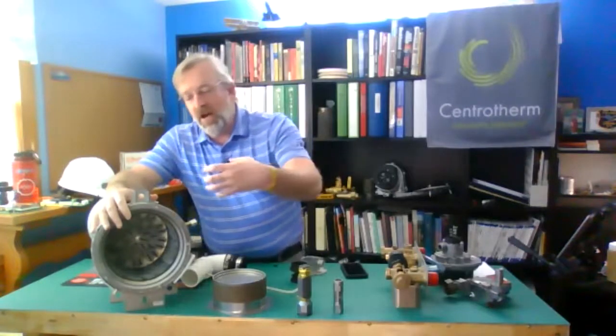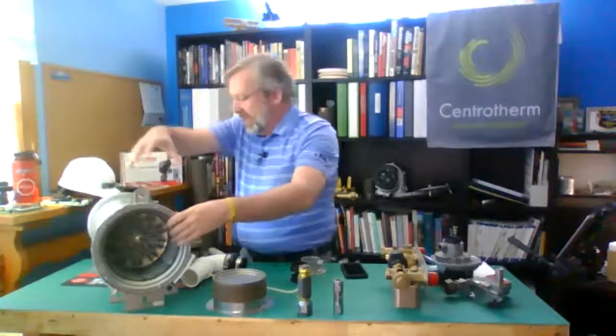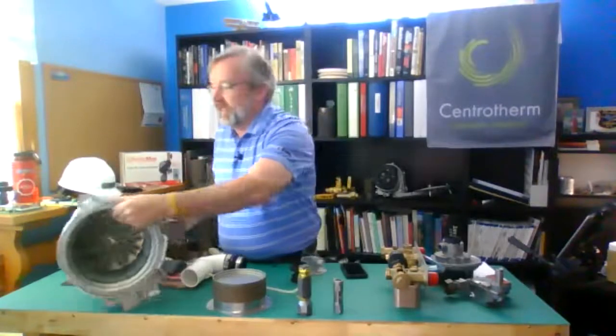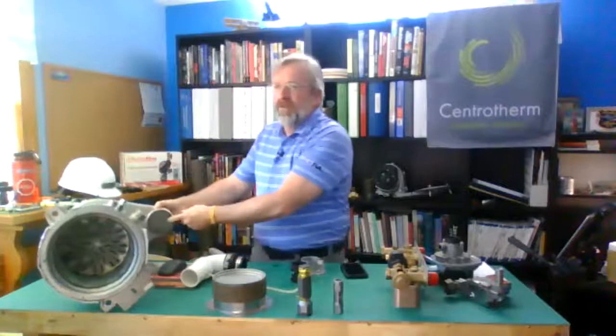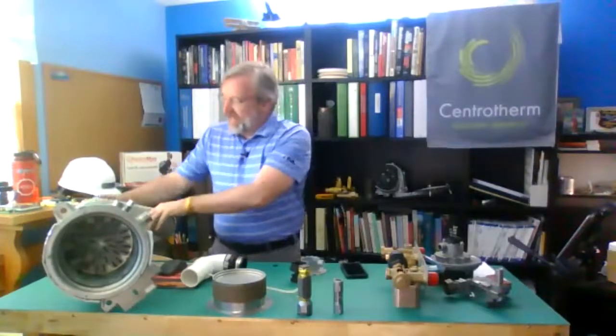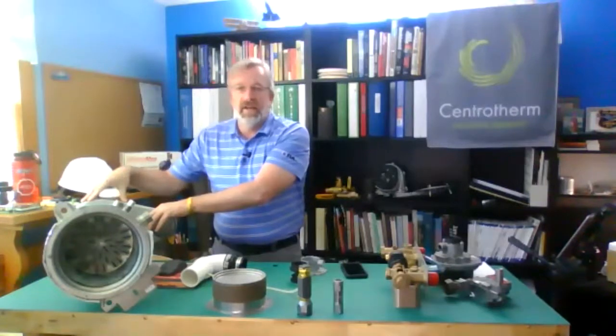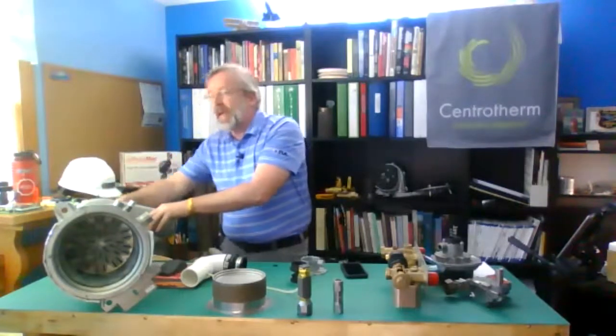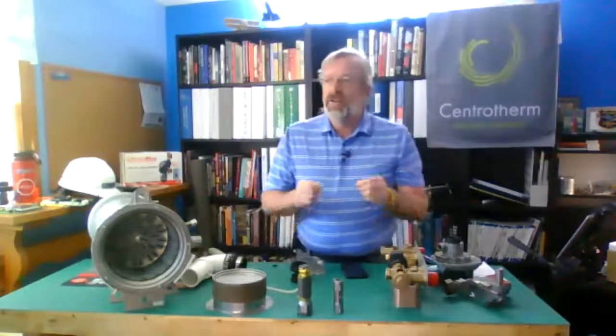Now, let's talk about that for a second. Why don't I see coffee grounds in here? Well, I'm down fired. I create a lot of velocity and turbulence. So what I'm actually doing is pushing all that leftover products of combustion down through my heat exchanger. Here's my flue collector down at the bottom, and right in the center of it, I have a condensate drain. The products of combustion come out through that condensate drain, which is why I get some calls and conversation with people asking, why is my condensate dirtier in my fire tube boiler than it is in my water tube boiler?